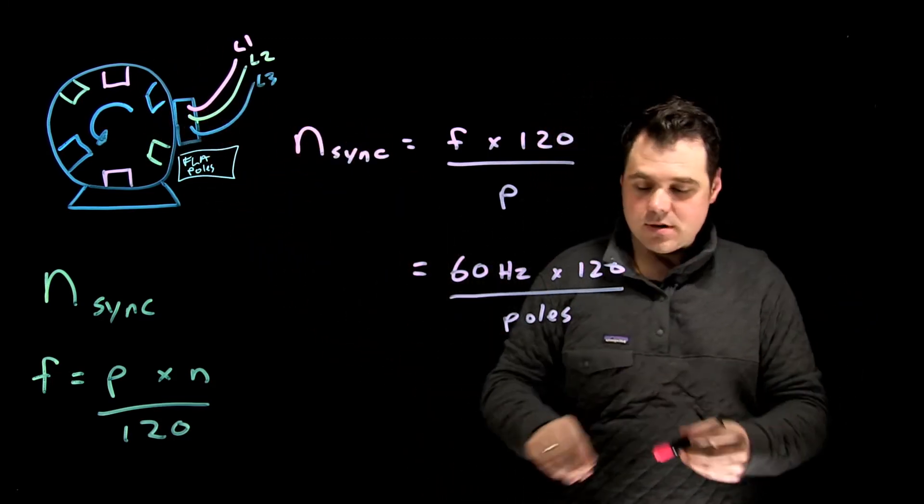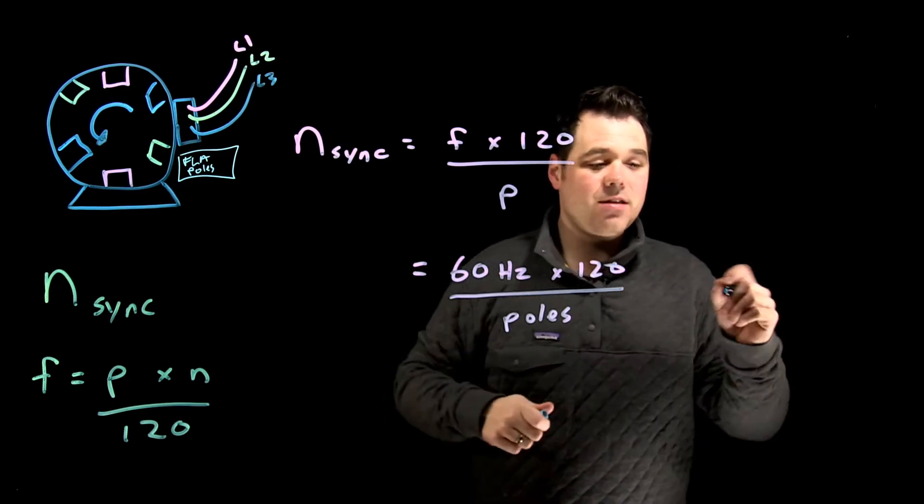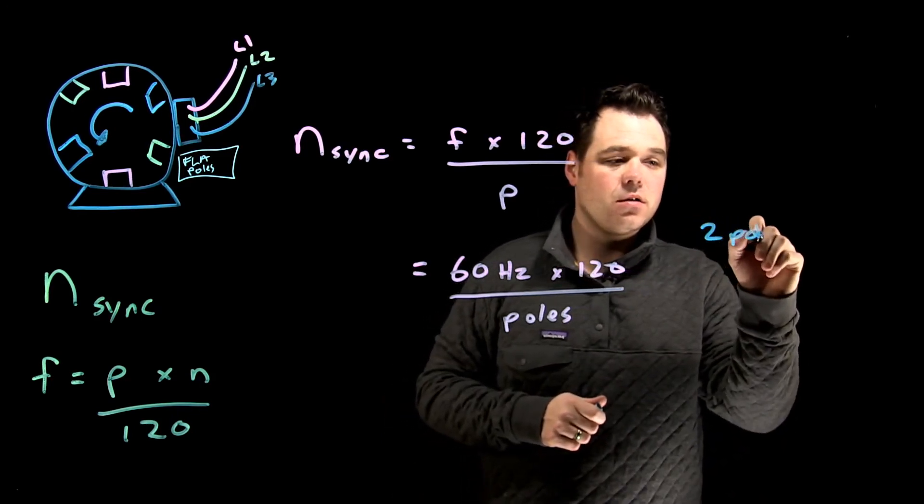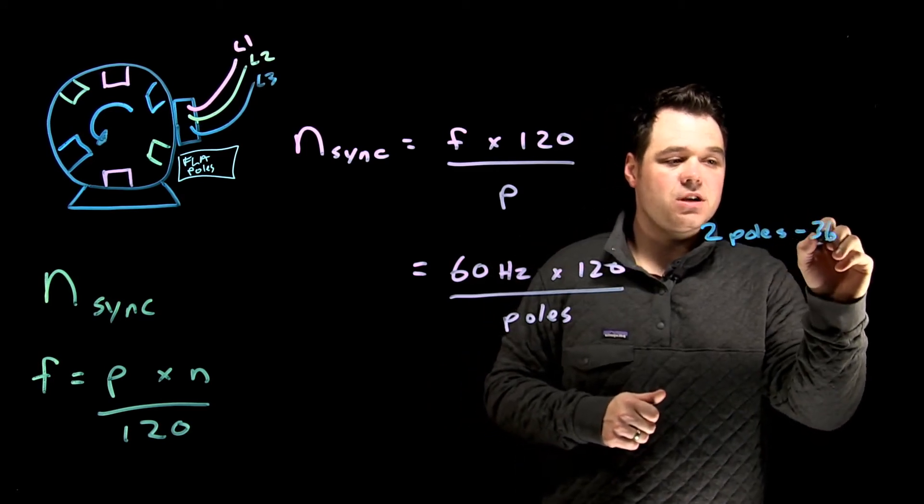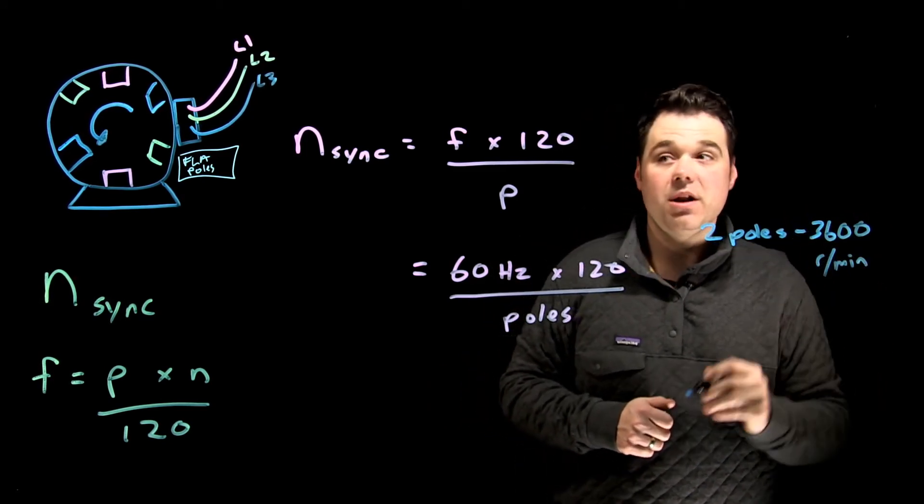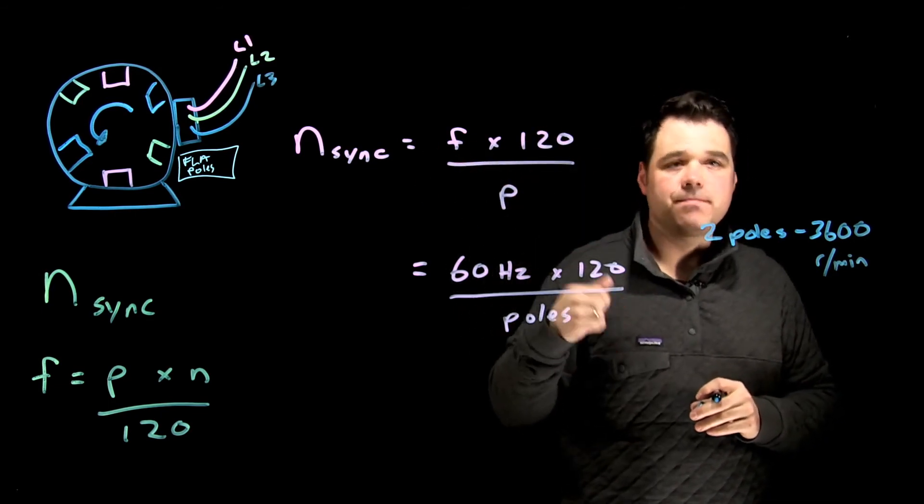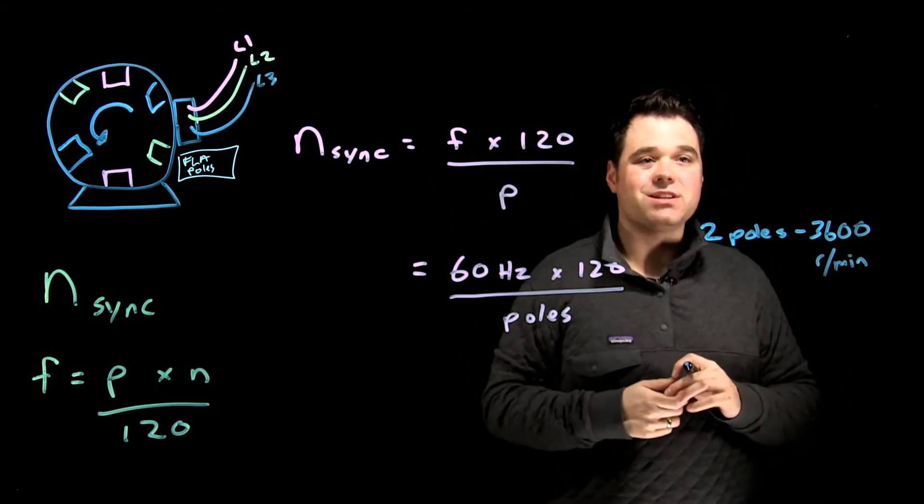So in this case with two poles, if we were to run that math, if we had two poles, our synchronous speed would be 3600 revolutions per minute. 60 times 120 divided by 2 gives us 3600.